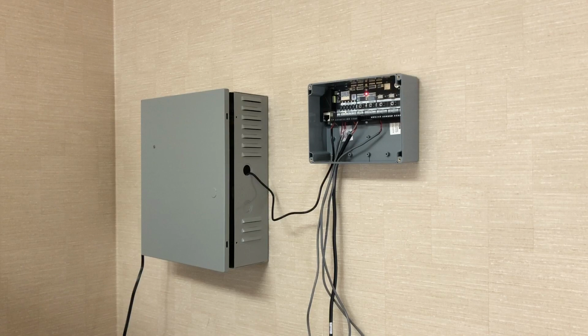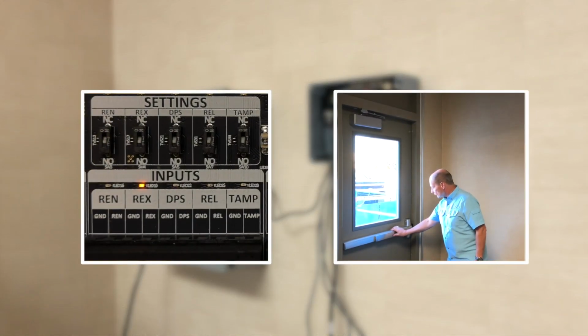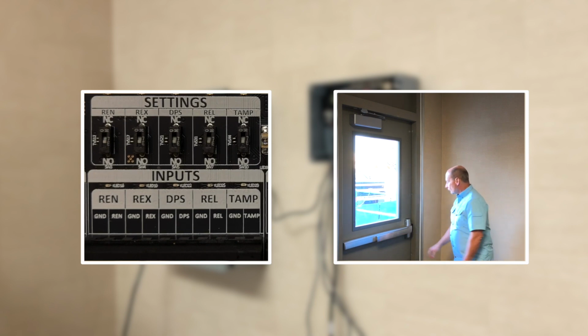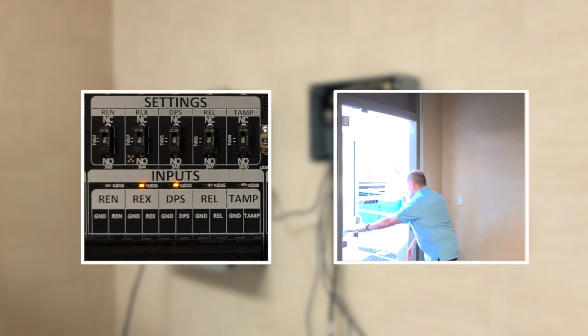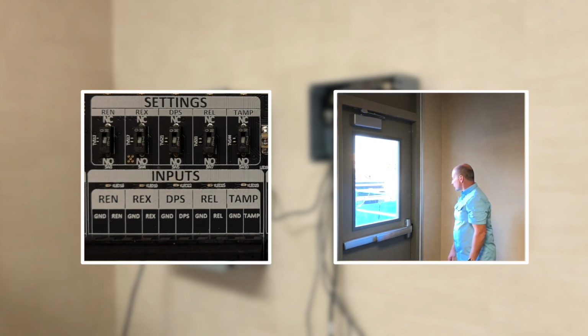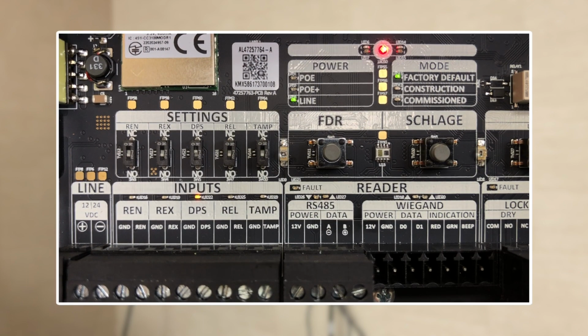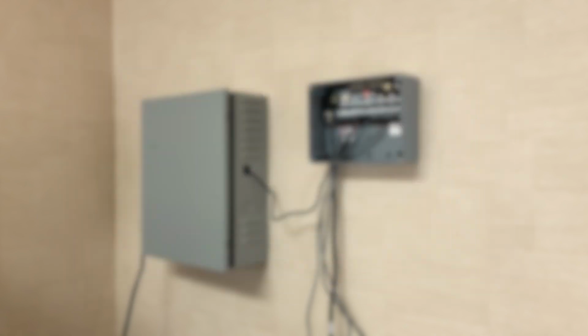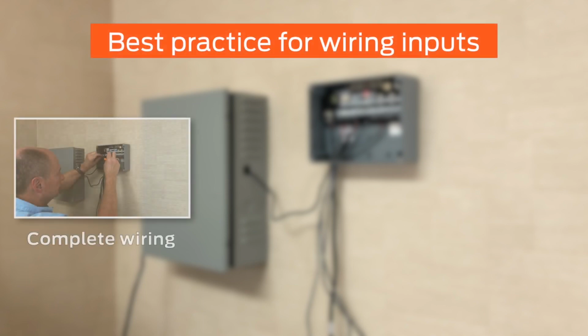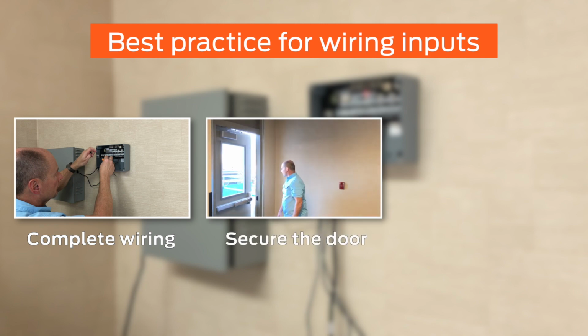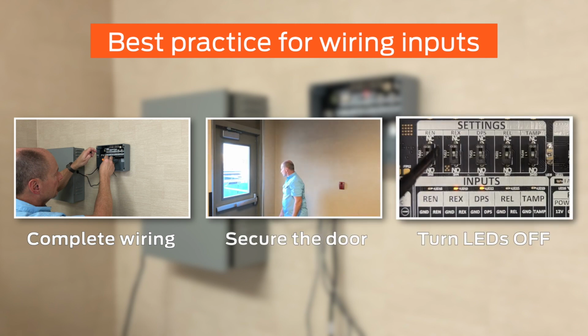Test each input by actuating the switch connected to it. For example, pressing the push pad for request to exit, or opening and closing the door for door position. The amber light above the switch will illuminate when active. If you find that any input has an LED on when the switch should be inactive, for example, if the DPS LED is on when the door is closed, flip the selector switch above it to the other position. The best practice for wiring and configuring inputs is to complete the wiring, put the door in a secure position, then flip the selector switch above any LEDs that are on. When all LEDs are off, the inputs are wired correctly.